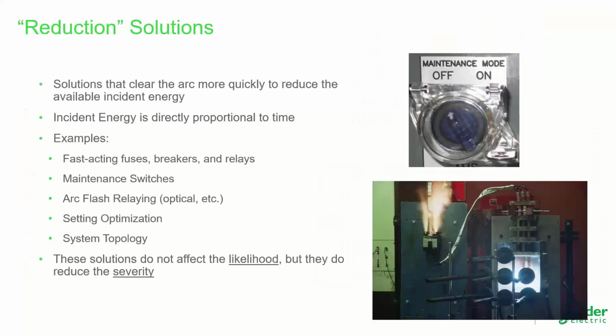But we can't prevent all arc flash events, so maybe we want to look at solutions that reduce the energy when they do occur. And so next category, reduction solutions that clear arcs more quickly in order to reduce the available incident energy. And this works because of that second bullet there. Incident energy is directly proportional to time. Now, if you've spent time looking in IEEE 1584 and seeing the equations that are in there, they're very complex and very involved. But one thing is very simple. Again, it's directly proportional to time.